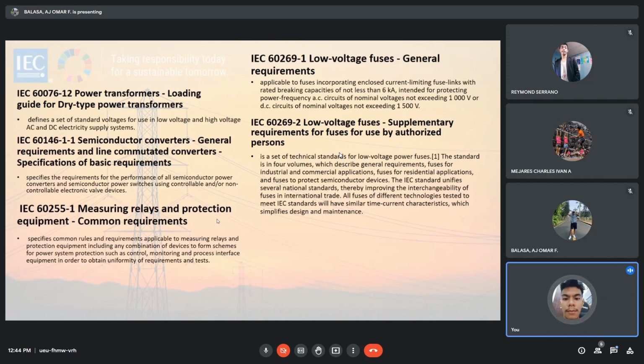Dito tayo sa IEC 60269 Part 2, Low Voltage Fuses, Supplementary Requirements for Fuses for use by authorized persons. Itong standard, IEC standard na to is para sa mga authorized persons. It is a set of technical standards for low voltage fuses. The standard is in 4 volumes which describe general requirements, fuses for industrial and commercial applications, fuses for residential applications, and fuses to protect semiconductor devices. The IEC standard unifies several national standards, thereby improving the interchangeability of fuses in international trade. All fuses of different technologies tested to meet IEC standards will have similar time-current characteristics, which simplifies design and maintenance. Next.